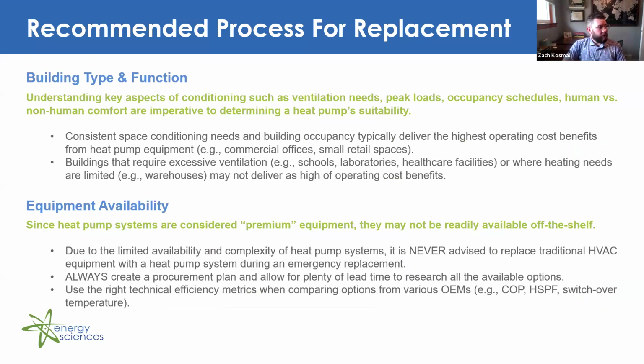So next we have building type and function. Understanding key aspects of conditioning, such as ventilation needs, peak loads, occupancy schedules, and human versus non-human comfort, is imperative to determining a heat pump's suitability. Consistent space conditioning needs and building occupancy typically deliver the highest operating cost benefits from heat pump equipment. Buildings that require excessive ventilation, or where heating needs are limited, may not deliver as high of operating cost benefits.